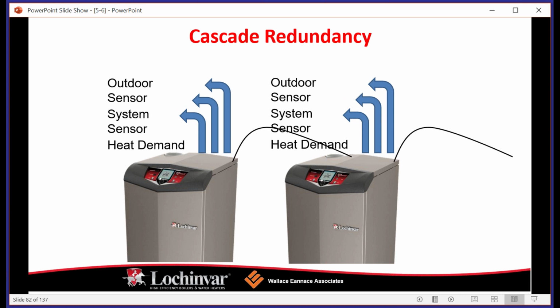It is significantly more efficient to have two boilers running at 25% of their input than it is to have one boiler running at, say, 50 or 60. And what the boilers are going to do is they're going to sequence themselves, right? So they're going to say, all right, this boiler's running a little too hot. Let's run two boilers down at the lowest fire rate possible. So again, that's what we're always striving to do, is to make sure we're using the least amount of fuel to create the correct amount of energy, okay?